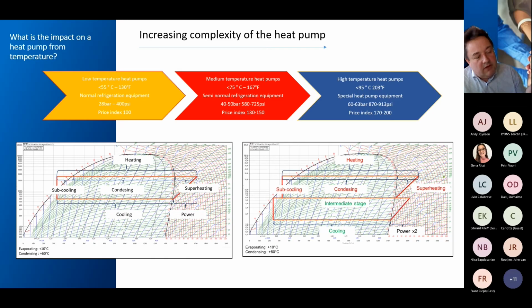So with this illustration, together with the consultants, we described a low temperature heat pump, actually using existing refrigeration technology that we use on a daily basis in food and beverage. Had we gone higher in temperature and lift, we would have moved into high pressure equipment with a 30 to 50% price increase on equipment and lower COP. So lift is associated with lower capacity and lower efficiency, meaning you are hit twice on your capex.